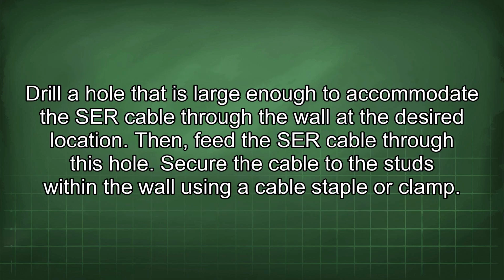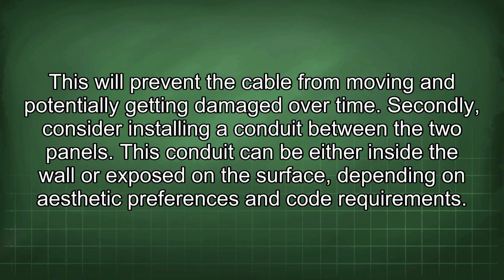Drill a hole that is large enough to accommodate the SER cable through the wall at the desired location. Then feed the SER cable through this hole. Secure the cable to the studs within the wall using a cable staple or clamp. This will prevent the cable from moving and potentially getting damaged over time.